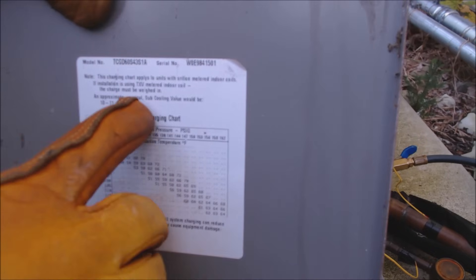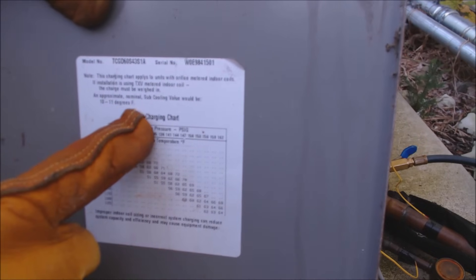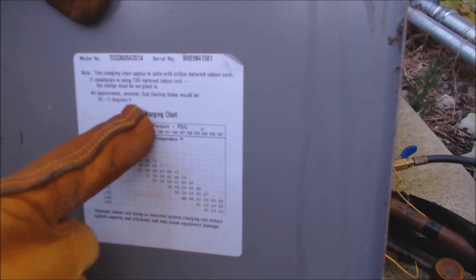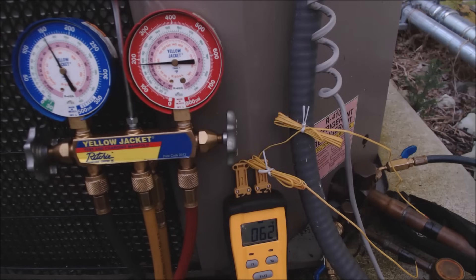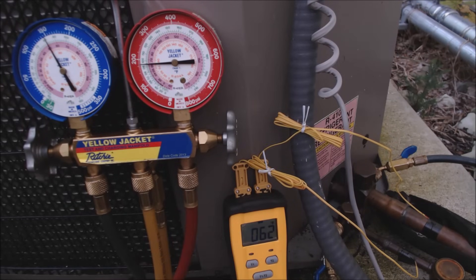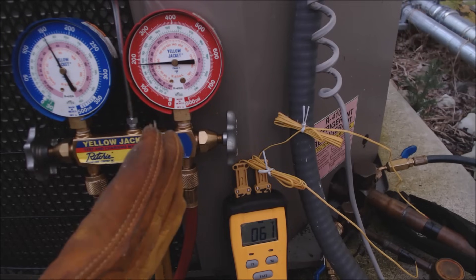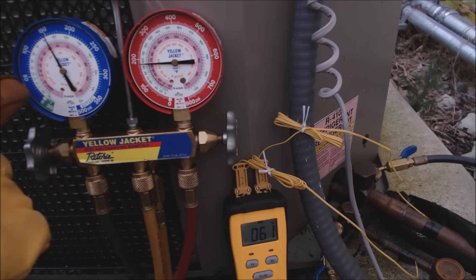The inside cover of the outdoor condenser calls for a nominal sub cooling value of 10 to 11 degrees Fahrenheit. The temperature has shifted to about 62 degrees with 64 degrees saturated, giving us only 2 degrees of sub cooling. Low sub cooling typically means you are low on refrigerant — however, if we were low on refrigerant, this pressure would be down lower.